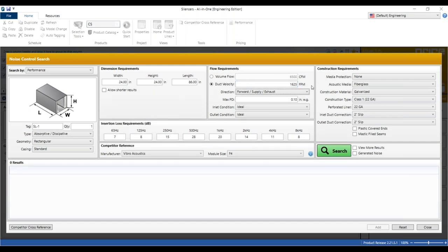Okay, so we had just over 1600 feet per minute forward flow. Right now, the schedule calls for ideal conditions. If you recall from yesterday's presentation, when you do the test for performance for silencers, you have five equivalent duct diameters of unobstructed ductwork that's not transitioning at the inlet of the silencer. And then you have 10 equivalent duct diameters at the outlet from the silencer to the reverberation room. You typically have that much room in any job that you size, 5 and 10 equivalent duct diameters.